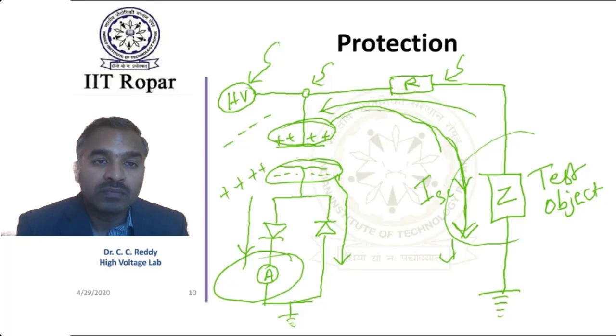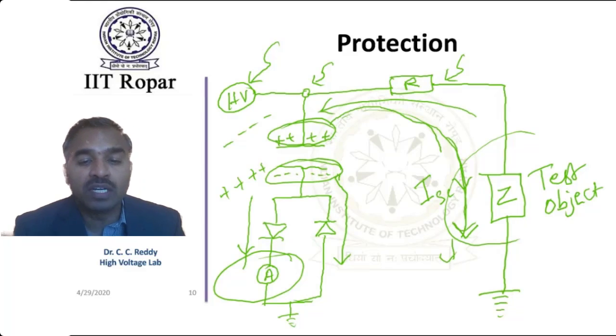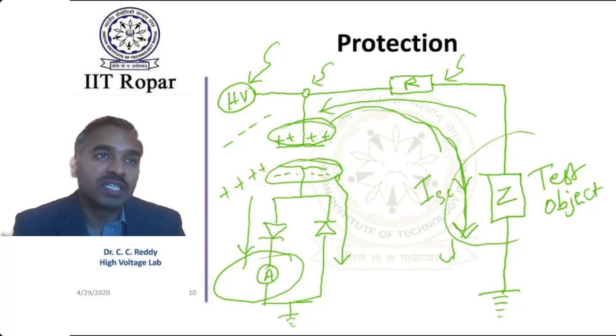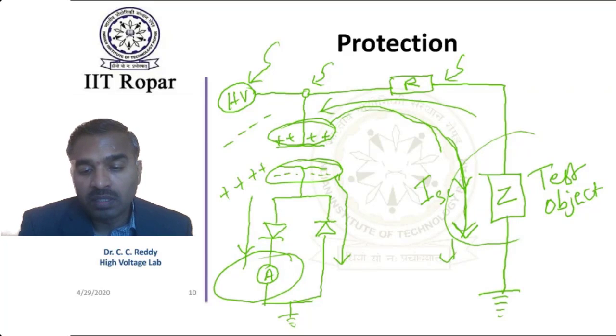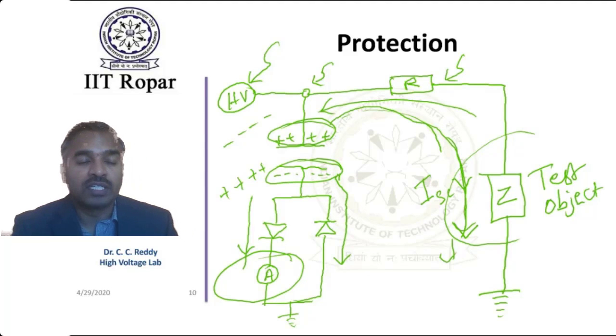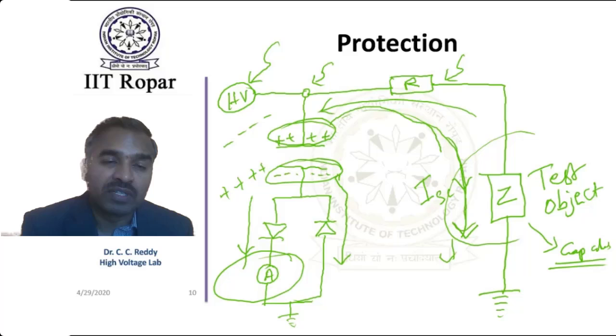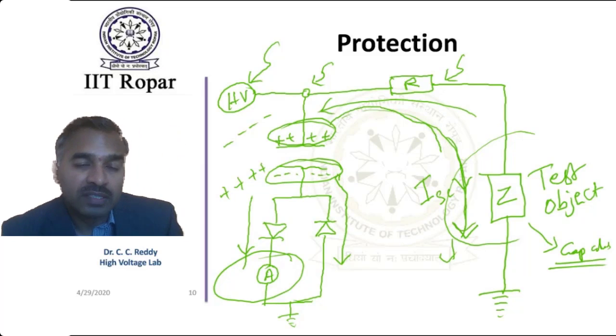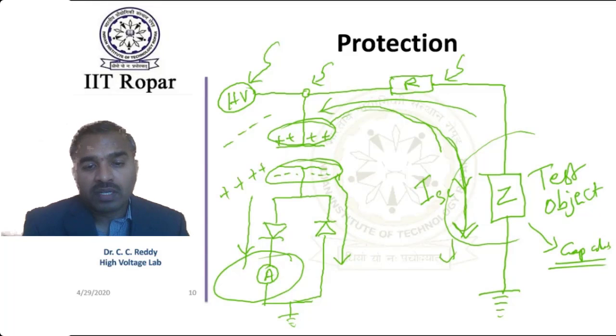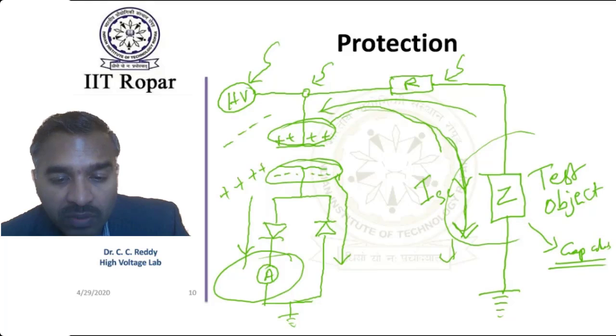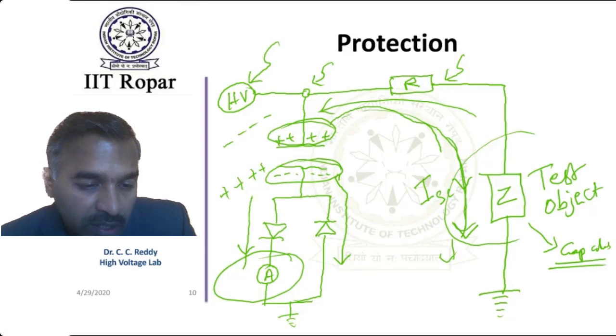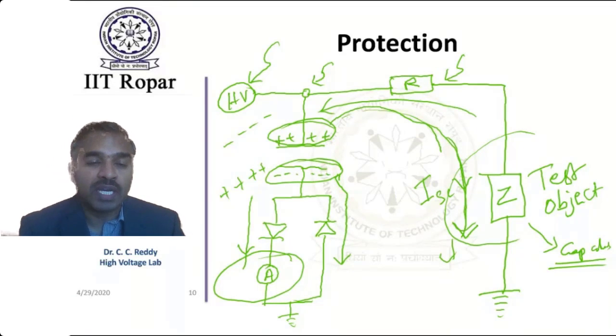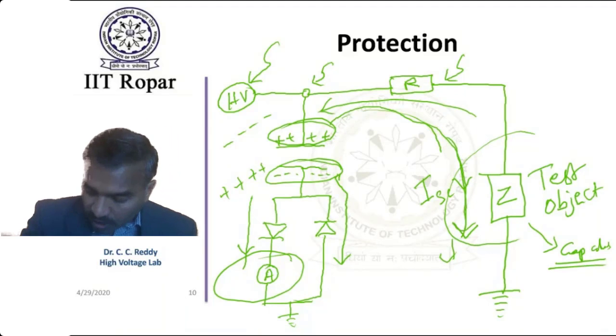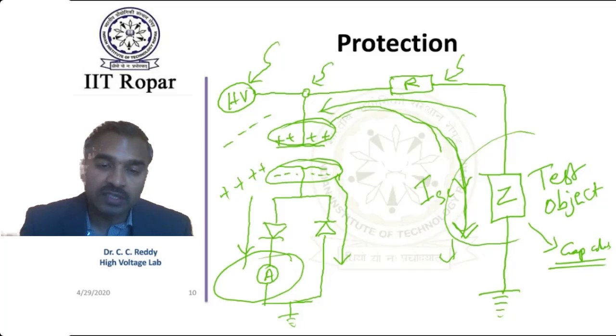But sir, the test object can be anything, right? It can be anything; we cannot control the test object, but normally the test object is connected such that it is basically a capacitance. In high voltage testing, it may be a motor with several turns, but the test we conduct has one terminal on the winding and another on the casing, so our interest is to test whether there is any problem with the structural insulation. That's how it is connected. You can assume it as a capacitor test object, but it does have stray values, stray inductances and resistances.